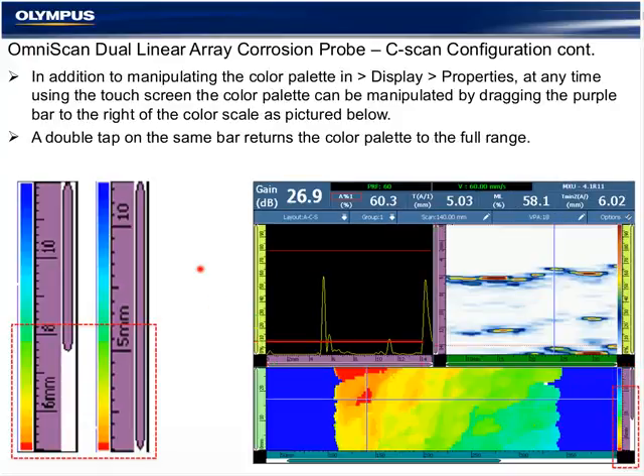It's normal to adjust the color palette both before, during, and after the inspection as conditions become known. The purple UT axis ruler is representative of the range selected, and then the color palette is scaled or applied over that. It can either be adjusted here directly on the C-scan right-hand column or under the display menu.